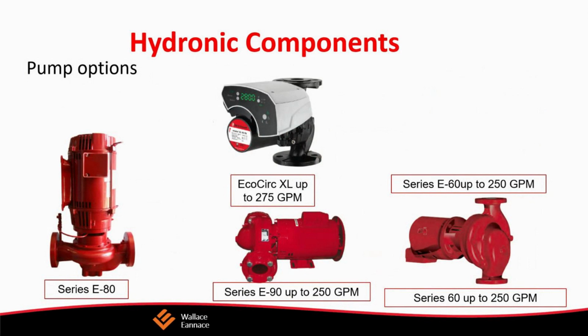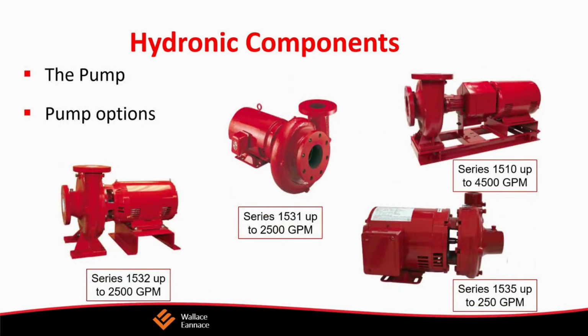Some other hydronic components with pumps include oil lubricated pumps, such as the Series 100 or the HV and that entire class of pumps. They have a motor, a coupling, bearing assembly, shaft, a seal, and an impeller inside the volute. Oil lubricated pumps are something that predominated a long time ago. You still see them out there. They're still pretty common, but they're sort of changing. And they've switched to permanently lubricated pumps, which is a little bit different.